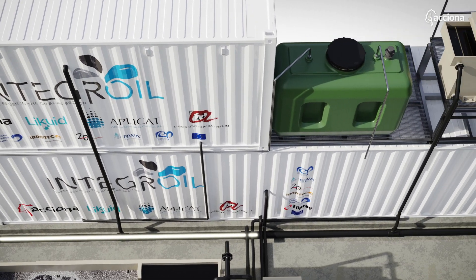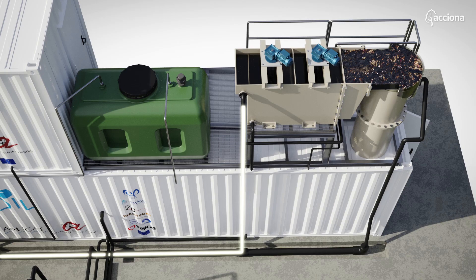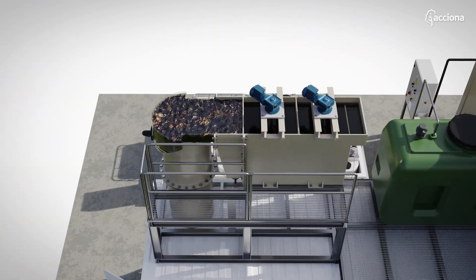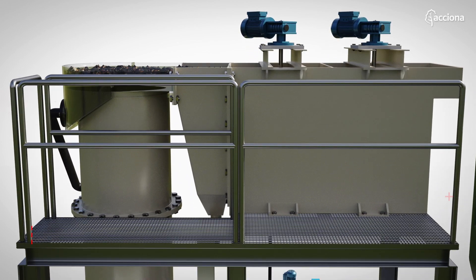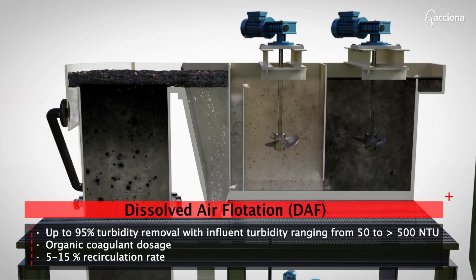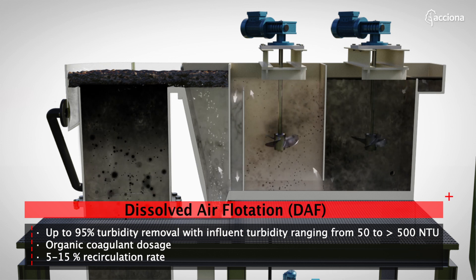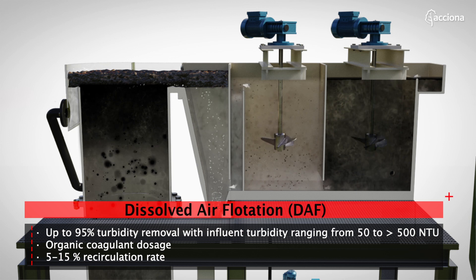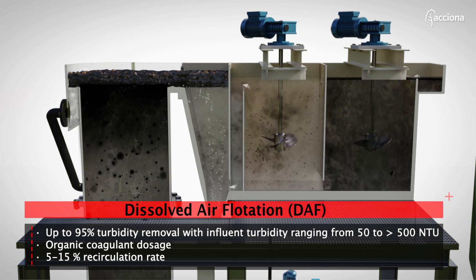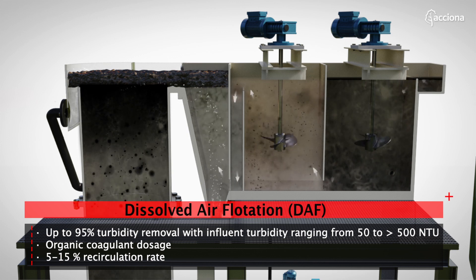Suspended matter present in the water is removed using a dissolved air flotation module. The removal is achieved by dissolving pressurized air in the water in a flotation tank basin. The released air forms tiny bubbles which adhere to the suspended matter, causing it to float to the surface of the water where it is removed by a skimmer.